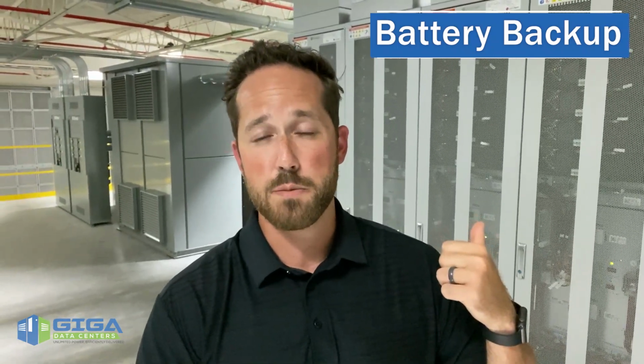The other job of the UPS is to ensure we're getting good power from the substation, from Duke Energy. If the UPSs ever notice we're no longer receiving power from the street, from Duke, they'll kick on the battery backups. From those battery backups, we have the ability to run this facility at about 6 to 7 minutes on 100% of the building load, strictly off these batteries.